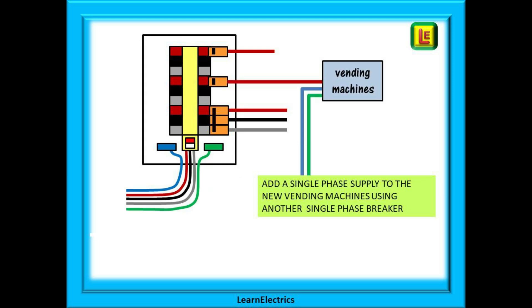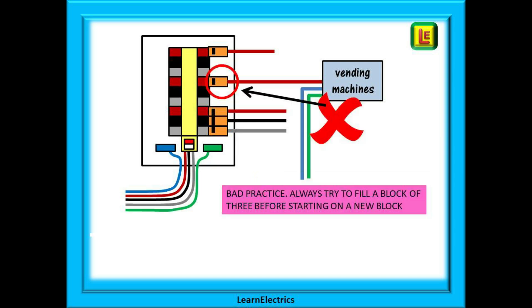Let's now add another single-phase circuit, perhaps for the vending machines in the new rest area. Again, we need a circuit breaker, a phase, a neutral and an earth. And we have connected the new breaker into the brown phase on another way or block. This is wrong. This is bad practice. Whilst the regulations do not forbid this, good working practice tells us that we should always try and fill up a way or block of three before starting a second block. The reason for this is that if we have single-phase breakers randomly spread around the distribution board, we may end up with no empty blocks of three when we need to install a new piece of three-phase equipment. Always try and work in threes.